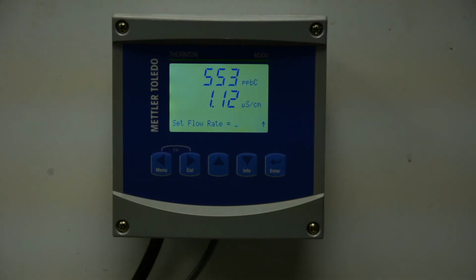Alright, and this is my last reading, 553 parts per billion. My second reading was also 553, so that's going to give me an average with 554, 553, and 553 of 553 parts per billion. So I'm going to write that down on my paperwork, then I'm going to do the math on what the response calculations are and the response efficiency, and find out what my percentage is and see if it passed the suitability test.